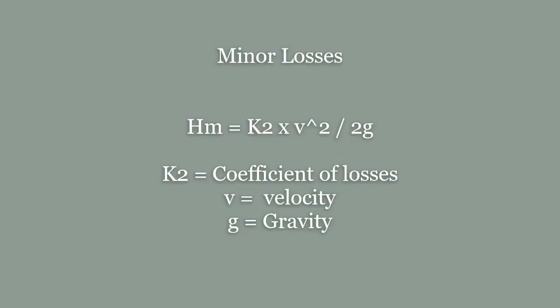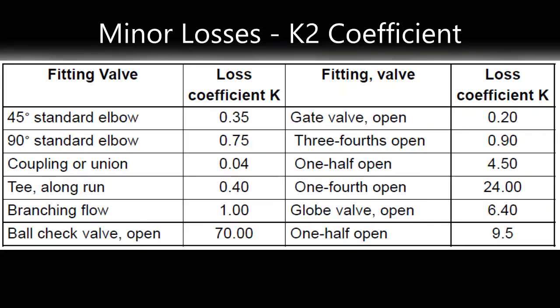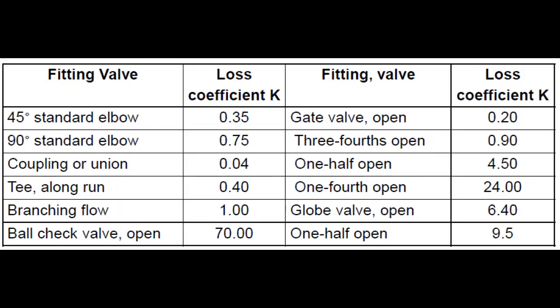Finally, the minor losses, which is the head losses due to fittings, valves and specials can be calculated using the following formula. HM equals K2 times V squared divided by 2 times G. K2 is the coefficient of losses for the fittings, specials or valve. V is the flow velocity and G is the gravity. K2 can be obtained from the design guidelines from the authority or the developer who is having jurisdiction.